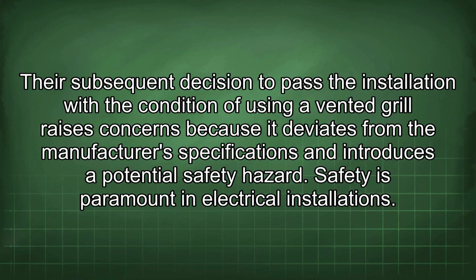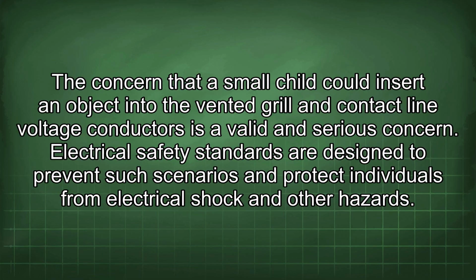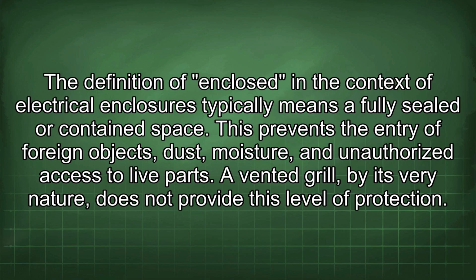Safety is paramount in electrical installations. The concern that a small child could insert an object into the vented grill and contact line voltage conductors is a valid and serious concern. Electrical safety standards are designed to prevent such scenarios and protect individuals from electrical shock and other hazards. The definition of enclosed in the context of electrical enclosures typically means a fully sealed or contained space. This prevents the entry of foreign objects, dust, moisture, and unauthorized access to live parts. A vented grill, by its very nature, does not provide this level of protection.